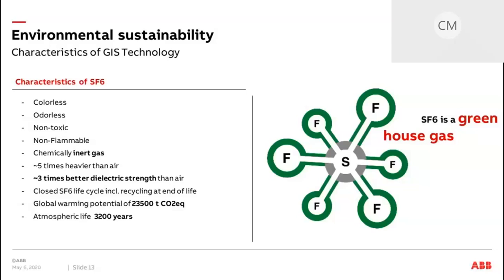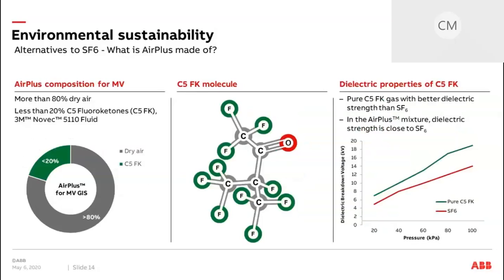Practically, it should be a closed life cycle, so the switchgear is filled in our factory and delivered to site. There is no gas works required during installation. And at the end of the lifetime, the service could evacuate the switchgear and recycle the gas. However, in some regions, especially in Europe, politicians discuss a ban on SF6. The answer to this could be the use of AirPlus.